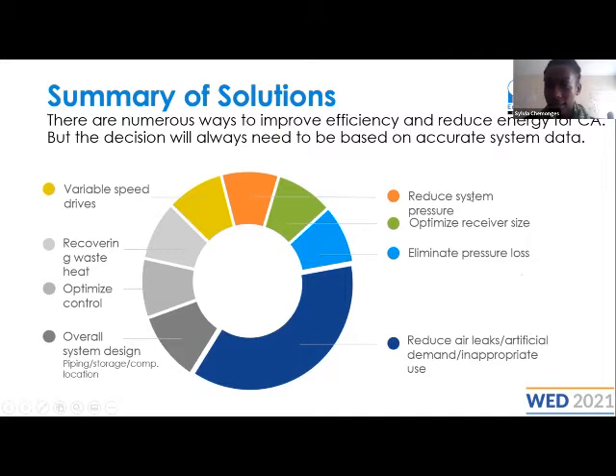And then another thing would be to reduce the overall system pressure. Reducing your overall system pressure reduces the artificial demand. If your compressor requires 6 bar, supply 6 bar. Do not supply 7 bar. That extra 1 bar is going to cost you a lot in the long run.